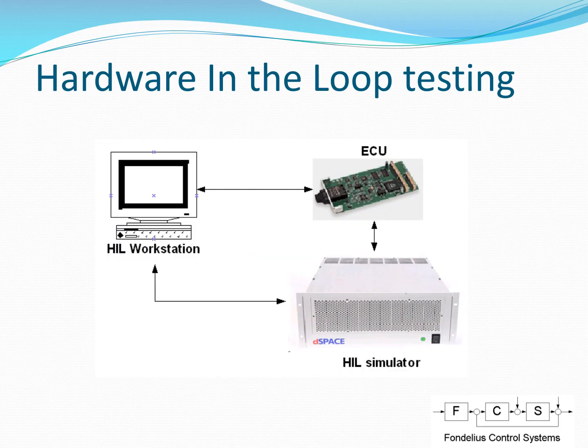To complete the hardware in the loop test bench we need to add the HIL workstation. By communicating with the converter control board and the HIL simulator it can configure both of them, introduce actions in both of them, log data and check conditions in both of them. This makes the HIL test bench an extremely powerful test environment and very suitable for test automation.